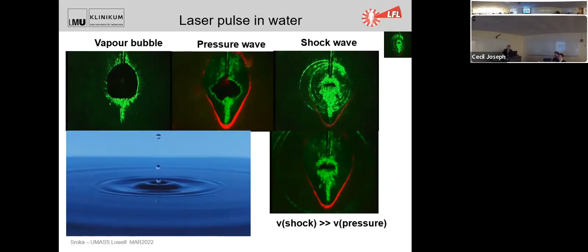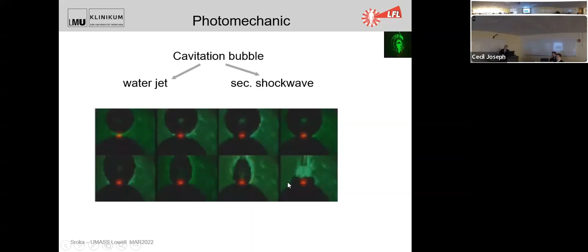So there is another point when this is a stone, and this is the vapor bubble right now. Then the vapor bubble is sometimes attached to the stone. The red light here is from the pilot laser, and here you can see that it is more attached to it, and then it is really not going free, but the whole energy is attached more and more to the target here, and sometimes a water jet is coming in. The water jet also reacts with the stone and makes some fragmentation process.